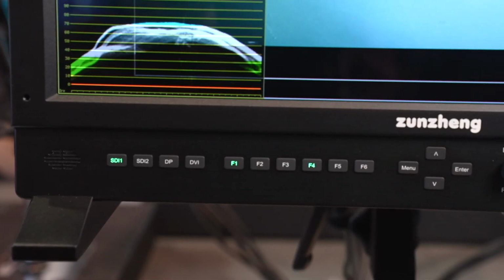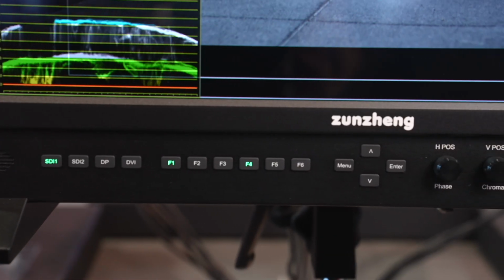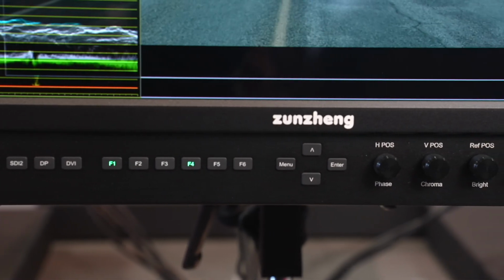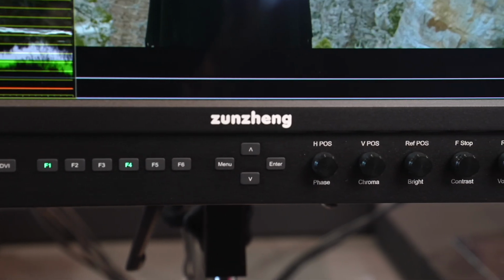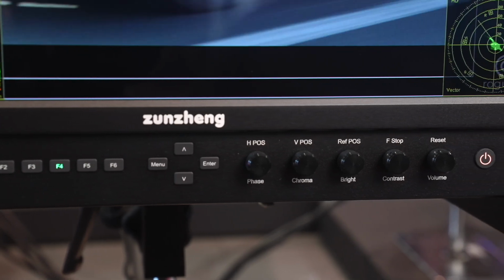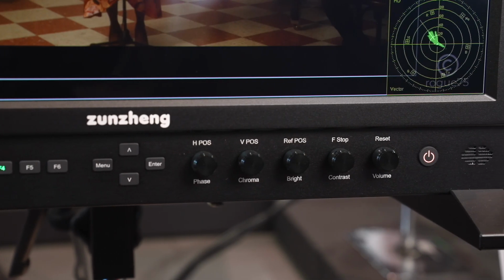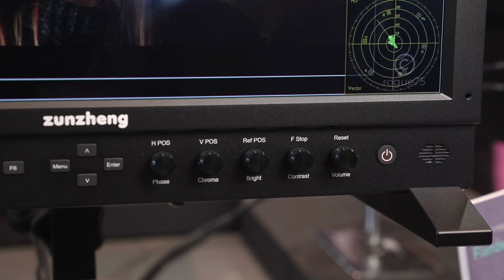But we also offer now a direct connect volumetric auto calibration, which is a very simple process, 4 steps on the monitor. We integrate with affordable probes like the X-Rite probe or the i1 probe from X-Rite. In less than 10 minutes you can calibrate your monitor and get it back up to spec without having to send it to us and without having to download additional software like CalMan or ColorSpace, which we also sell if people want to use that. The direct connect volumetric auto calibration has virtually no learning curve and will give you accurate results, and you keep your monitor within spec for many years to come.